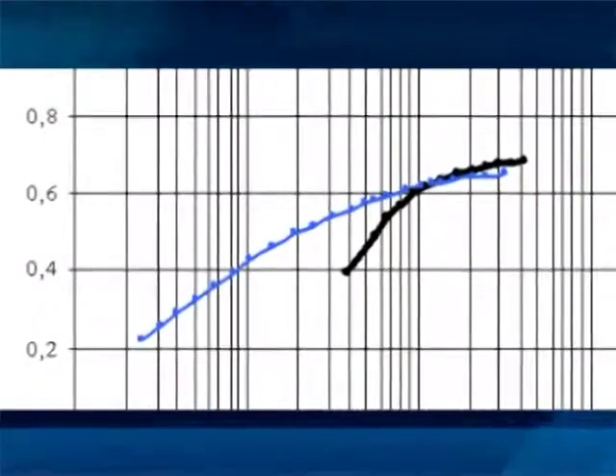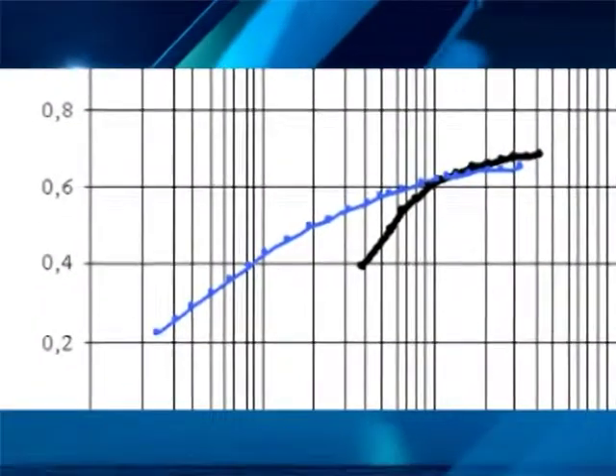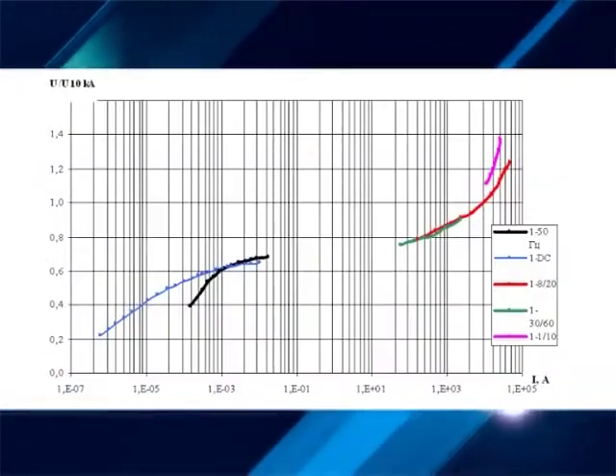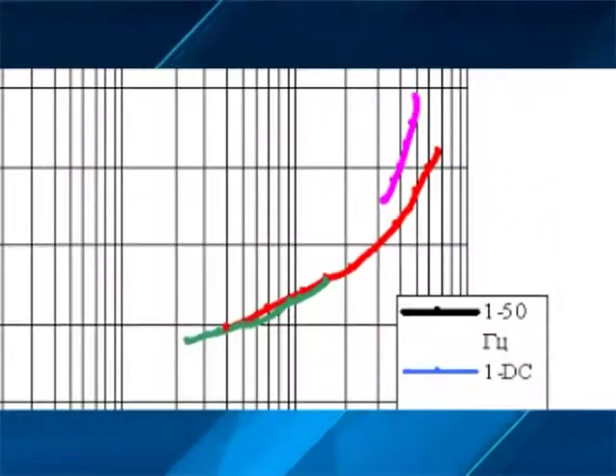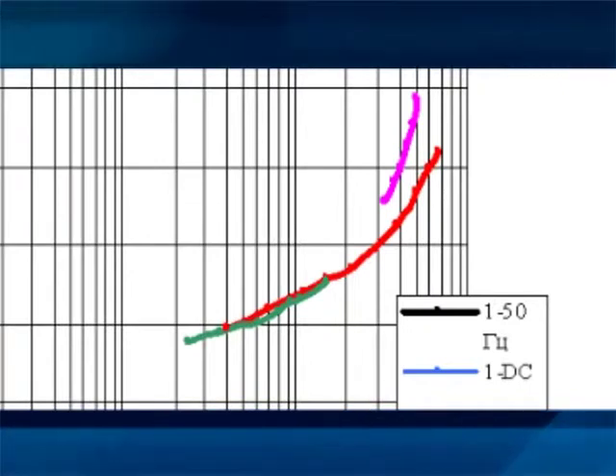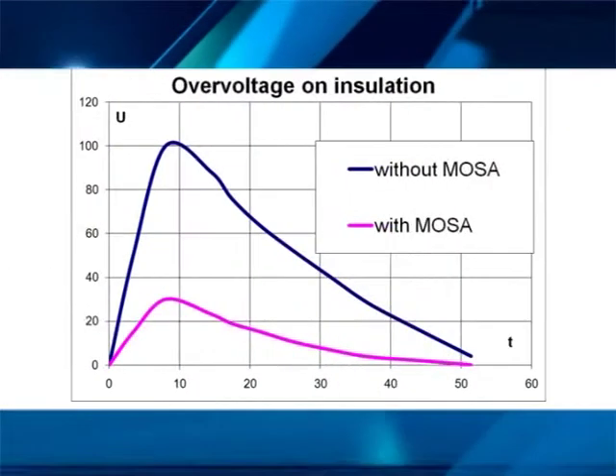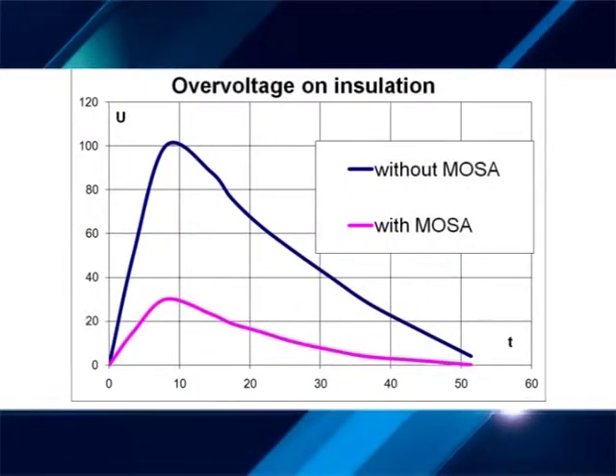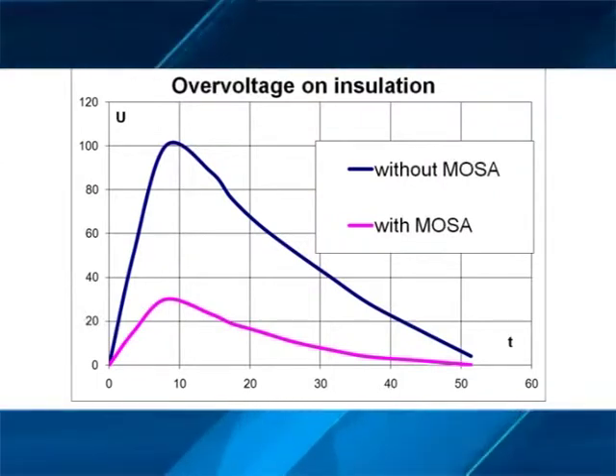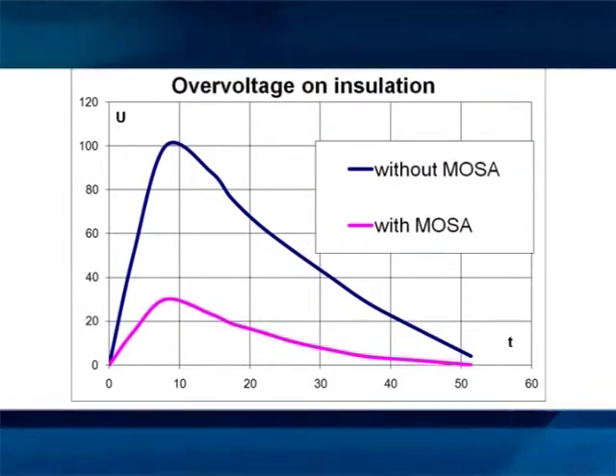Under operating voltage, current through varistors doesn't exceed fractions of a milliampere, but during overvoltage, hundreds and thousands of amperes are reached. Surge arresters let energy surges through into the ground, while the overvoltage in the grid becomes limited to a permissible level for the electrical insulation.